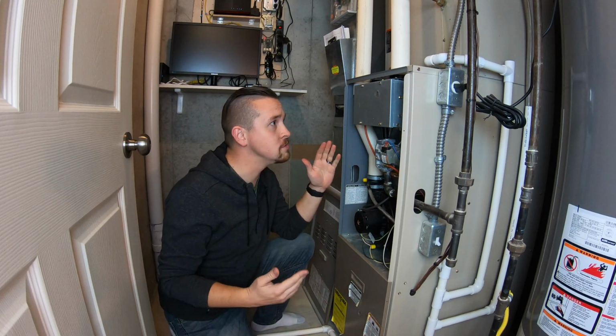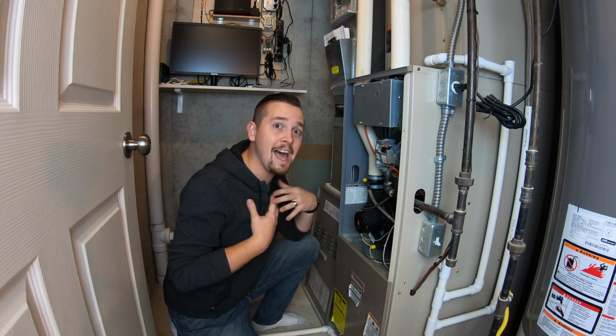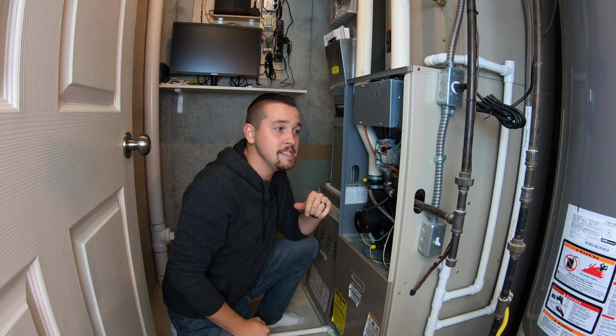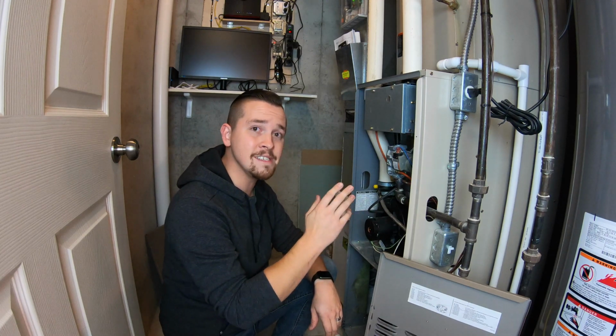Dirty flame sensor is one of the most common repairs that I find as a technician. And it's a very simple thing to fix. Normally the symptom that you'll see is the burners light and turn right back off within 3 seconds.